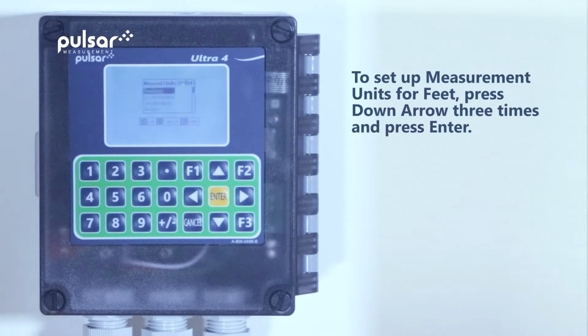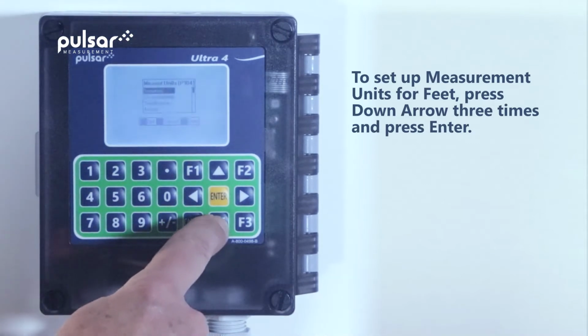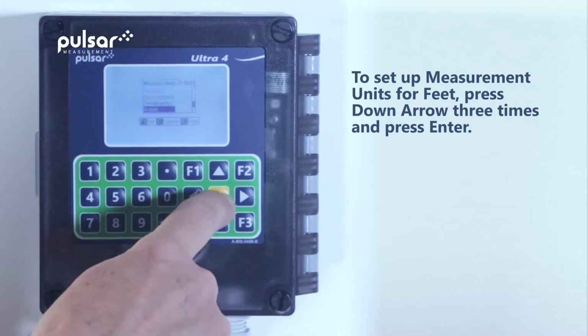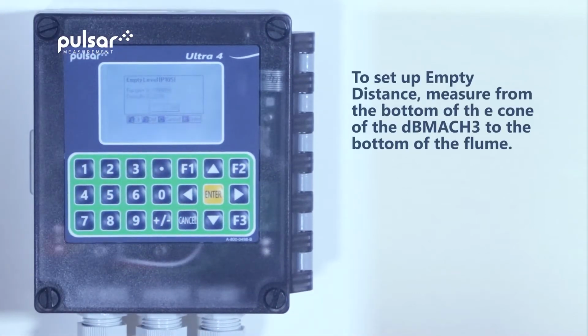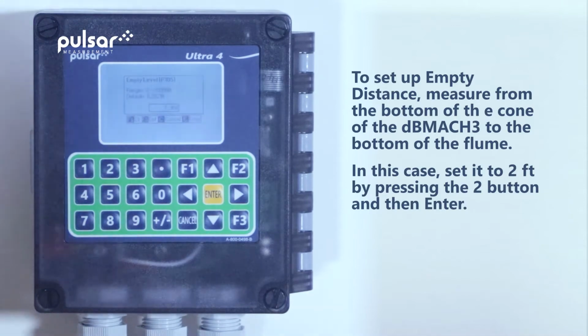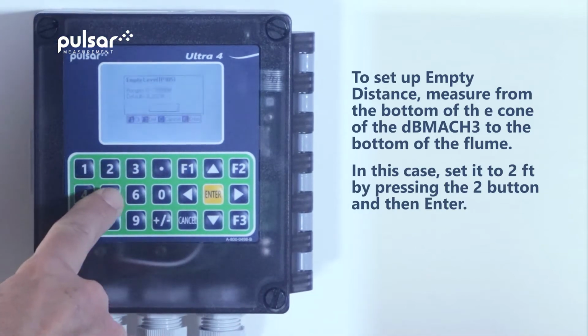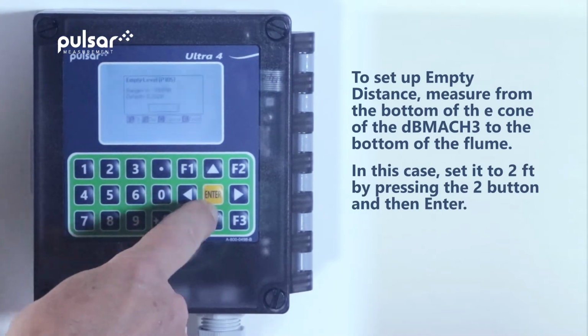Time to set up the measurement units. For this application, we'll be using the measurement unit of feet. We'll hit the down arrow button 3 times and then enter. To set up the empty distance, we'll want to measure from the bottom of the cone of the dB Mach 3 to the bottom of the flume. In this case, we'll set 2 feet as that parameter. We'll hit the number 2 and then the enter button.